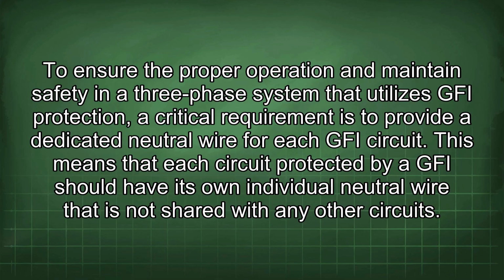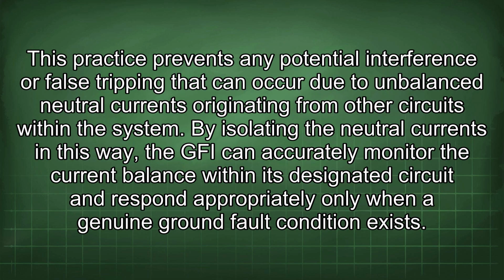This means that each circuit protected by a GFI should have its own individual neutral wire that is not shared with any other circuits. This practice prevents any potential interference or false tripping that can occur due to imbalanced neutral currents originating from other circuits within the system. By isolating the neutral currents in this way, the GFI can accurately monitor the current balance within its designated circuit and respond appropriately only when a genuine ground fault condition exists.